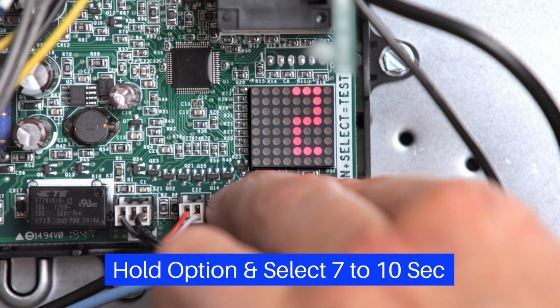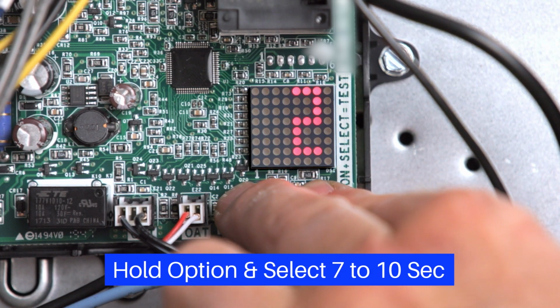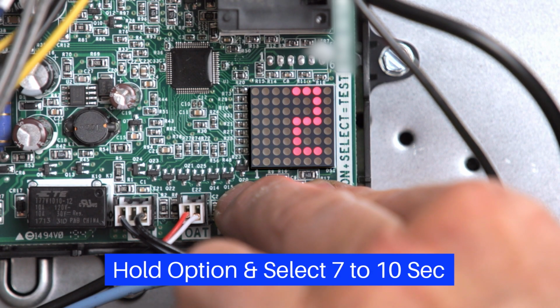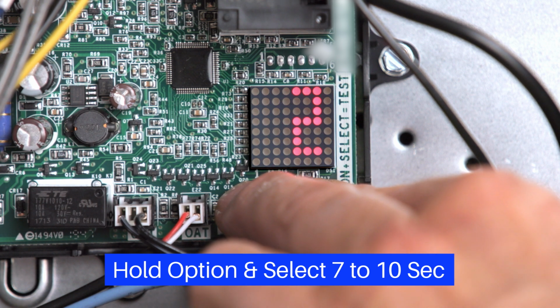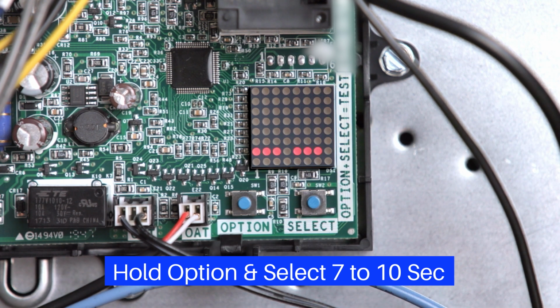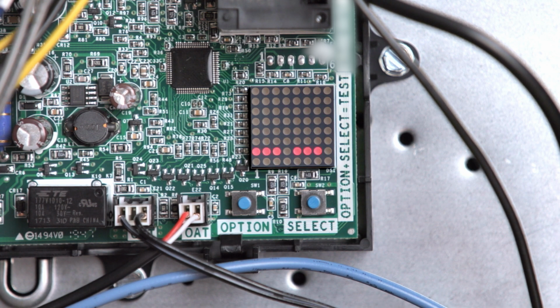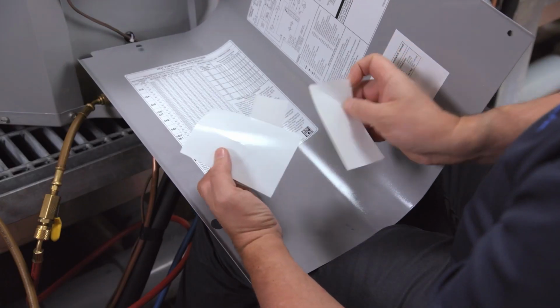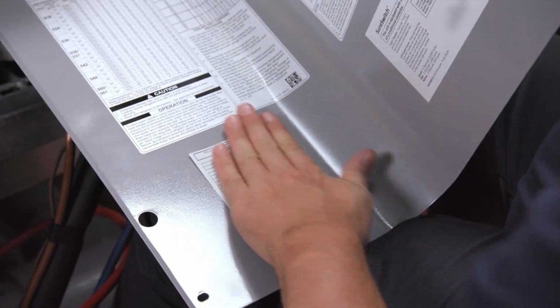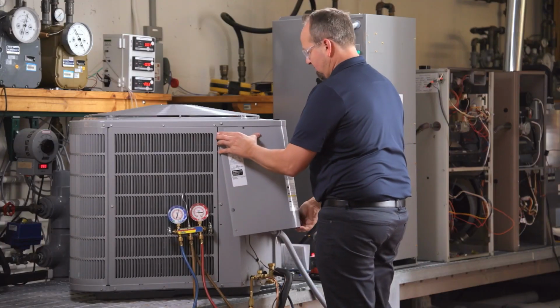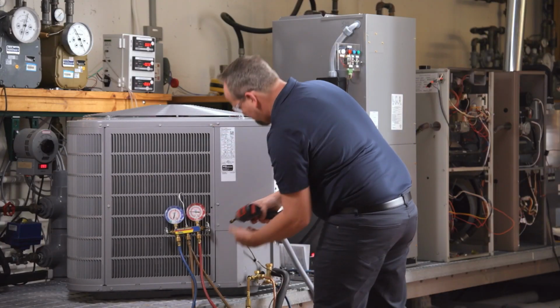To clear stored faults, hold the Option and Select buttons for greater than 7 seconds and less than 10 seconds to clear all faults. The display will flash 2 underscores 3 times to indicate the faults are successfully removed. Install the control label and reinstall any panels that were removed.